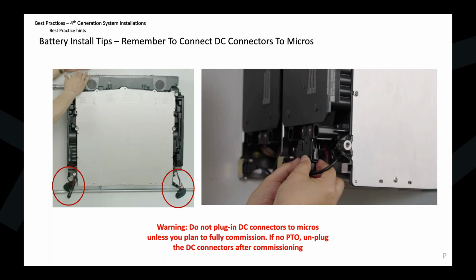And let's see, there was another question regarding how to do whole home backup or partial home backup if the utility hasn't yet approved the meter collar. You guys may have talked about this earlier in the session, but basically that's when we look at using a standalone meter pan, or meter socket, as they're sometimes called. Essentially, that meter collar is not going to be put behind the meter itself because it's not approved for that, but you can still install it on top of a separate meter pan, which would be located electrically between the backup loads panel and the main panel for a partial home configuration, or between the meter and the main panel if you're doing whole home.